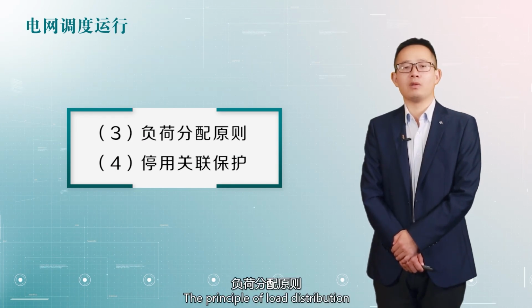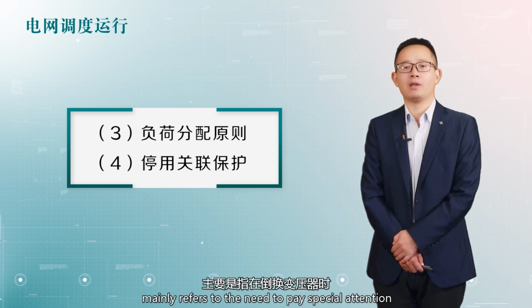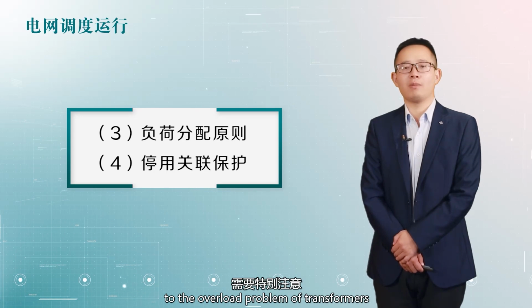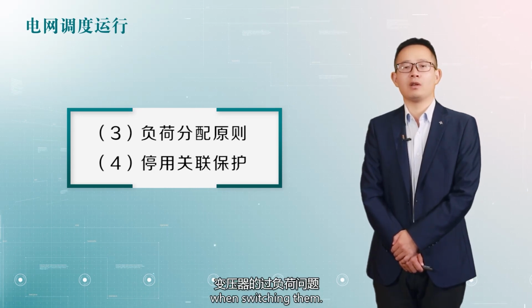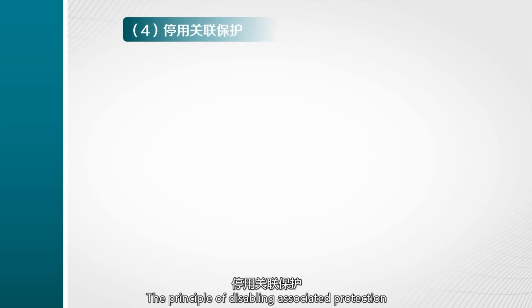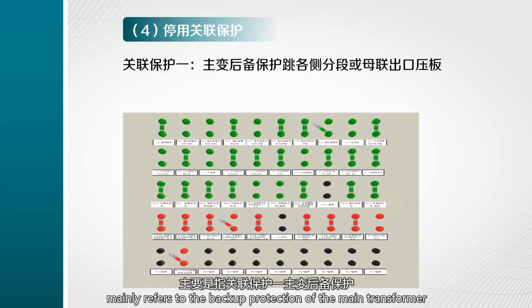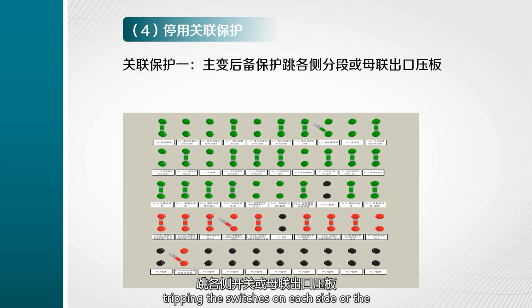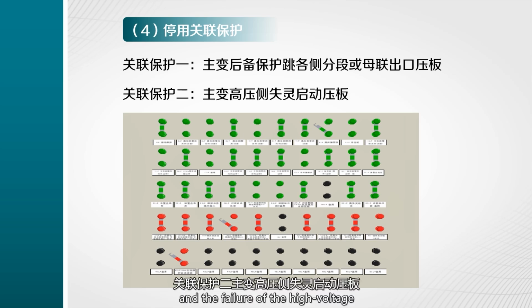The principle of load distribution mainly refers to the need to pay special attention to the overload problem of transformers when switching them. The principle of disabling associated protection mainly refers to the backup protection of the main transformers: tripping the switches on each side or the bus bar outlet pressure plate, and the failure of the high voltage side of the main transformer starting pressure plate.